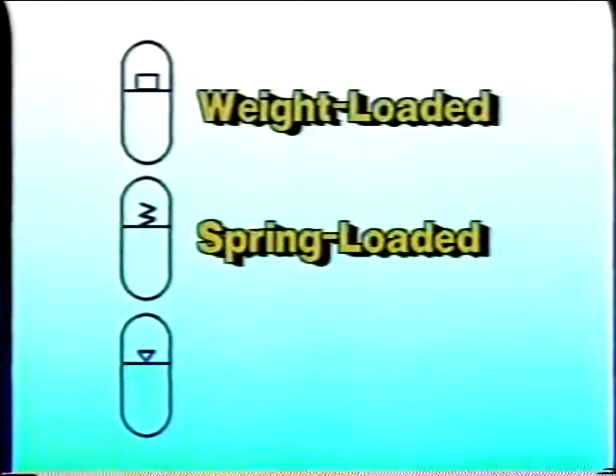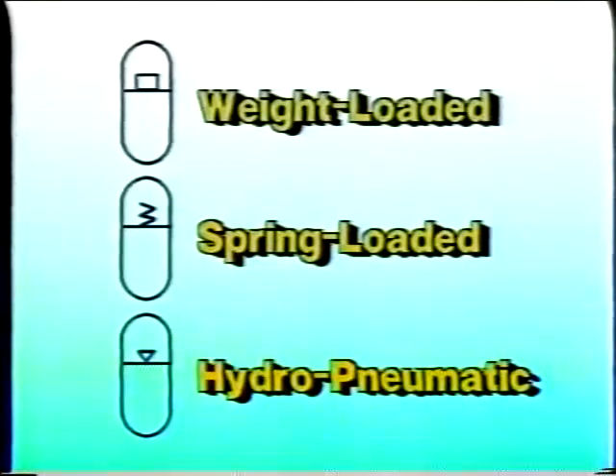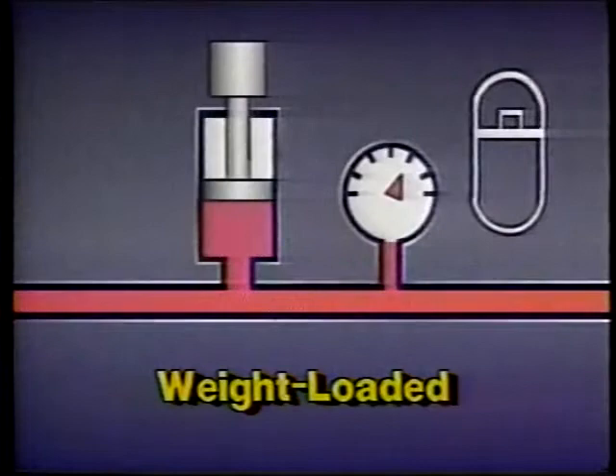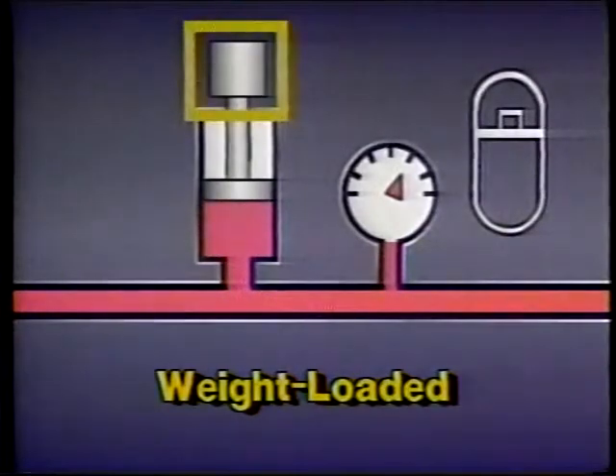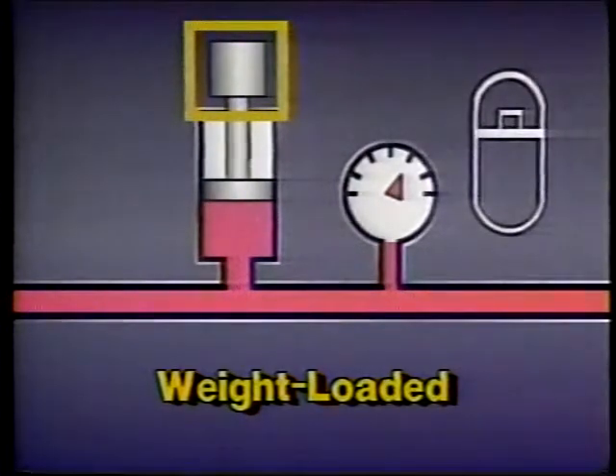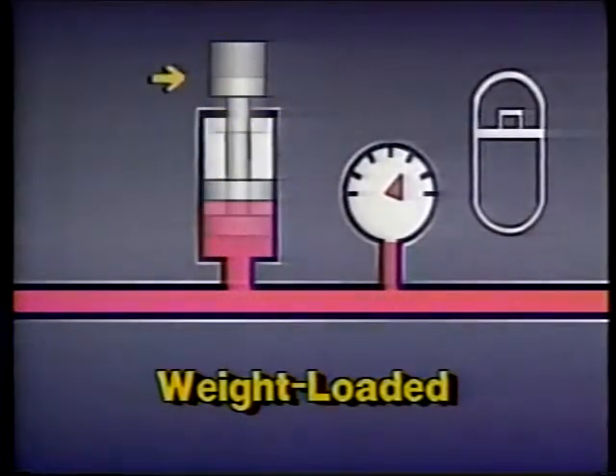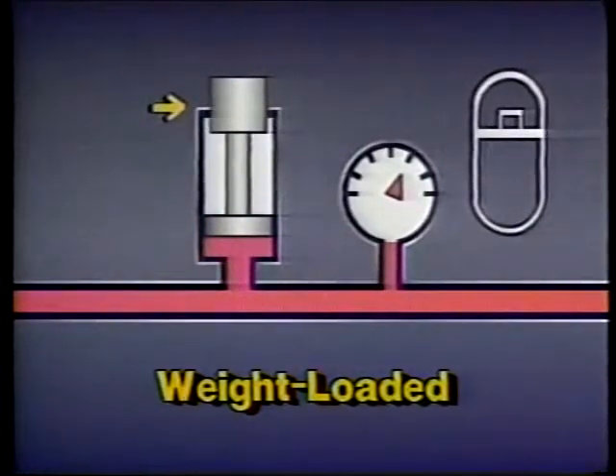Three types of accumulators are used: weight-loaded, spring-loaded, and hydro-pneumatic. Weight-loaded accumulators apply a force by means of weights. The weight can be of any heavy materials such as concrete, metal, or even water. Weight-loaded accumulators are usually large and they often service several hydraulic systems at once. This type of accumulator provides constant pressure because the weight does not change as the accumulated fluid is discharged.